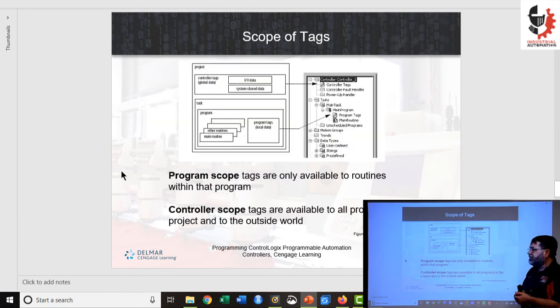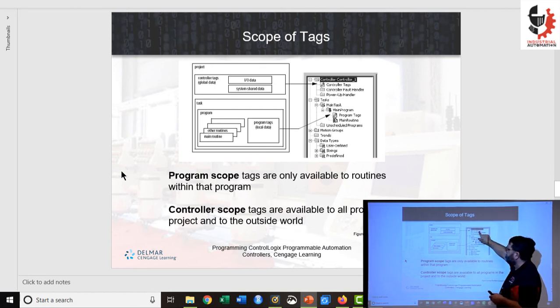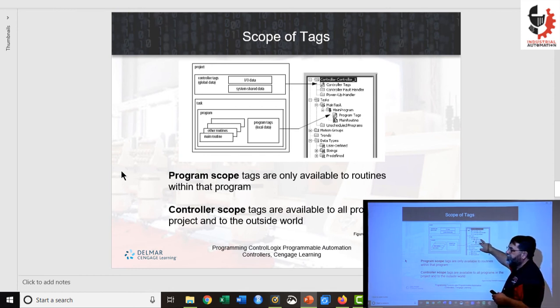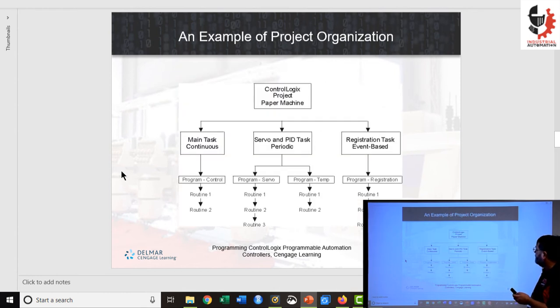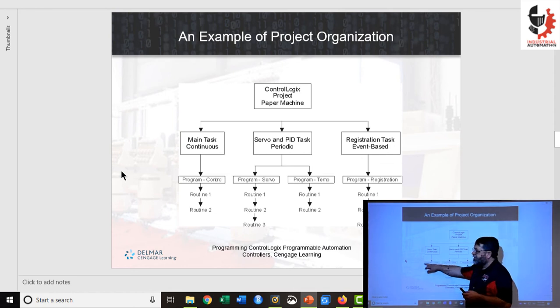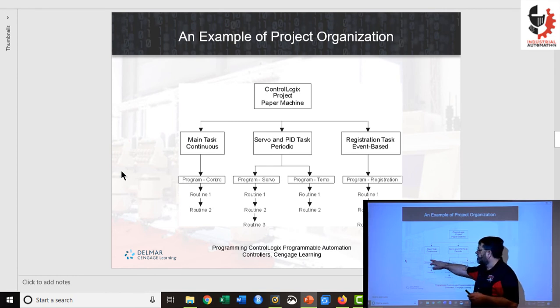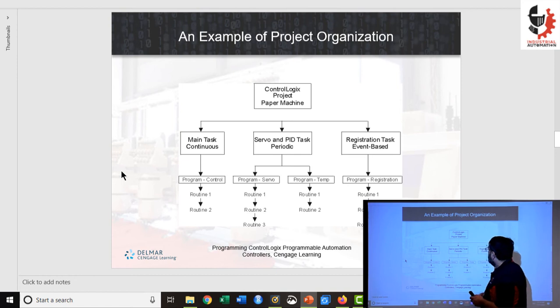Tags can be placed in different locations. Controller tags, as you can see in this hierarchy, can be used by any program in your project. We can also put tags inside individual programs, and those tags are only available to that program. For example, we could have a motor running tag in one program and a separate motor running tag in another program — they could refer to different motors. If we put tags up in the controller-level tags, those tags are available to everyone.